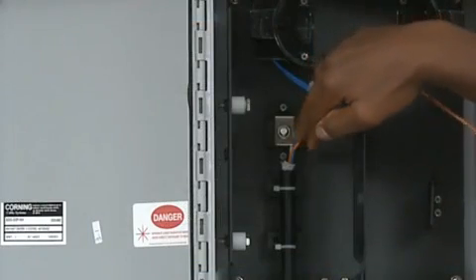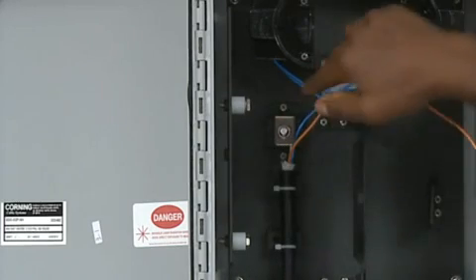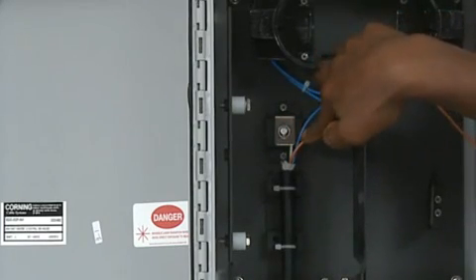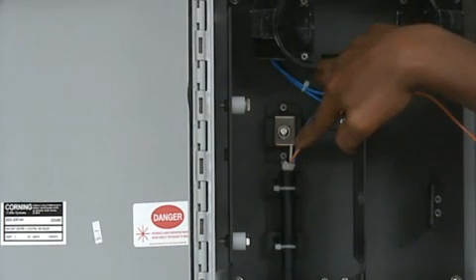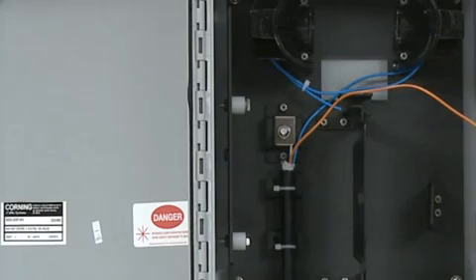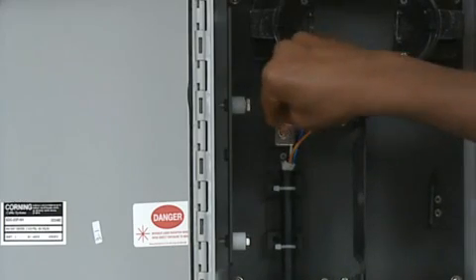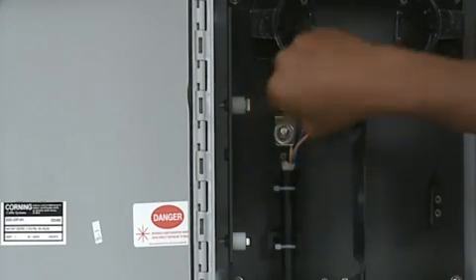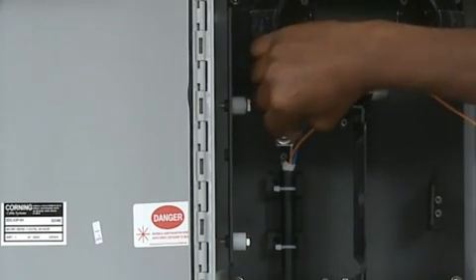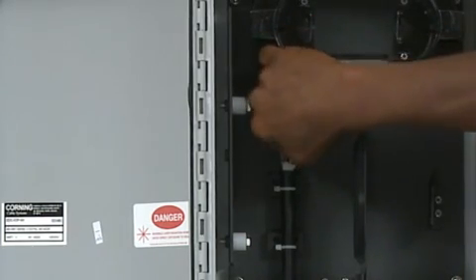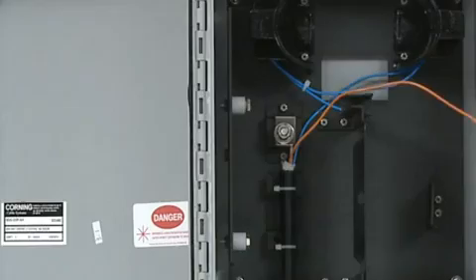My cable is also strain relieved. I'm using cable ties and I'm also securing the central strength member because for each cable that experiences temperature fluctuation in the last 10 meters, the central strength member has to be strain relieved. On top of this, one installs two flat washers which are used to capture yarn if it's present on your cable and that is that for cable strain relief.